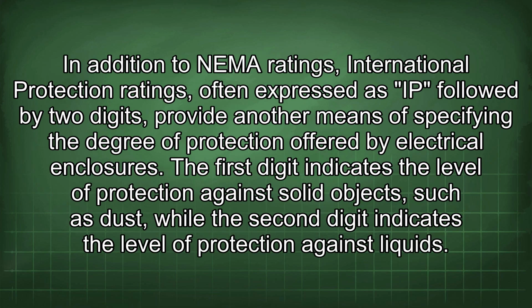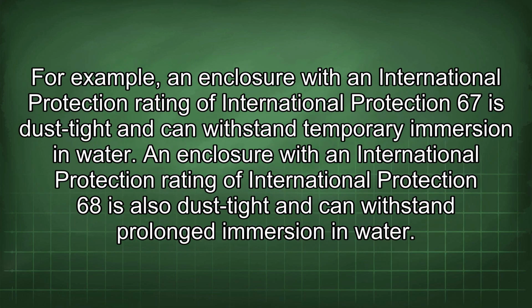In addition to NEMA ratings, international protection ratings, often expressed as IP followed by 2 digits, provide another means of specifying the degree of protection offered by electrical enclosures. The first digit indicates the level of protection against solid objects, such as dust, while the second digit indicates the level of protection against liquids. For example, an enclosure with an International Protection rating of International Protection 67 is dust-tight and can withstand temporary immersion in water. An enclosure with an International Protection rating of International Protection 68 is also dust-tight and can withstand prolonged immersion in water.